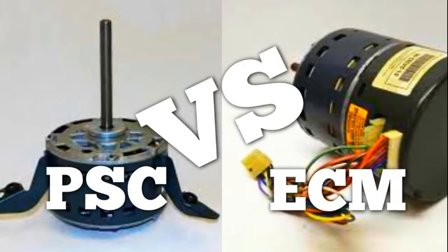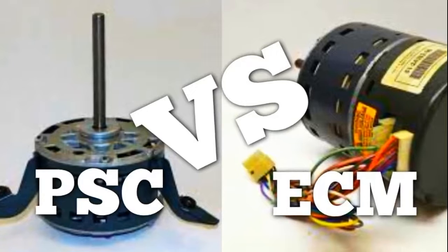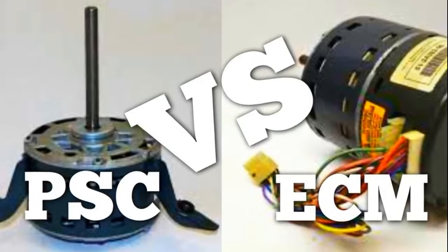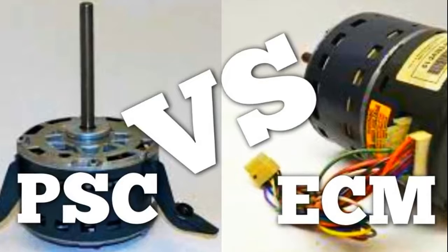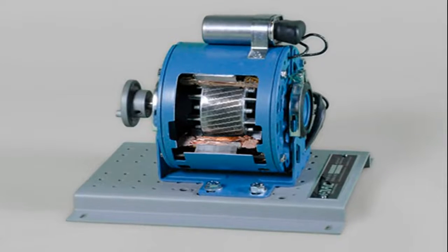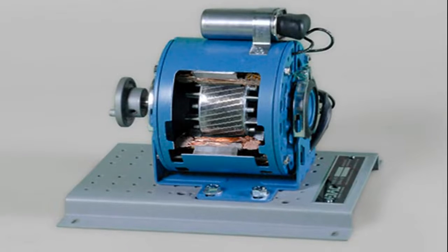The dynamic response is a motor's ability to react to changes in either operator demands or applied loads. A motor with good dynamic response can change speeds quickly and can compensate for a sudden change, such as increased or decreased airflow. ECMs can operate at many different speeds and, as a result, can handle variability with grace. On the other hand, PSC motors are inherently difficult to control without reducing efficiency and are sometimes referred to as on-off motors, as they have a tough time changing speeds. PSC motors therefore cannot respond as fast — or sometimes at all — to dynamic situations as ECMs can.